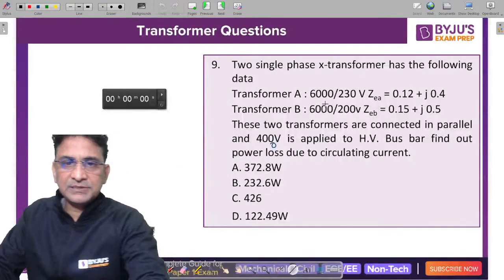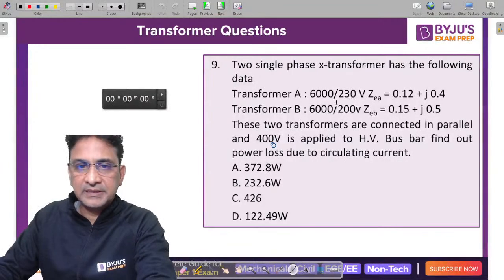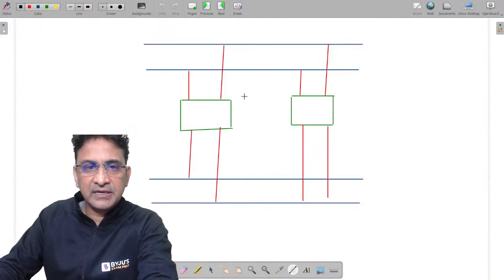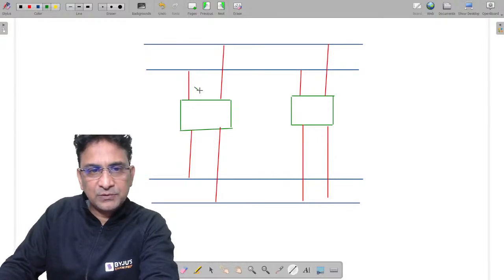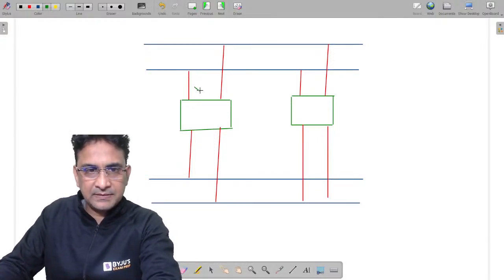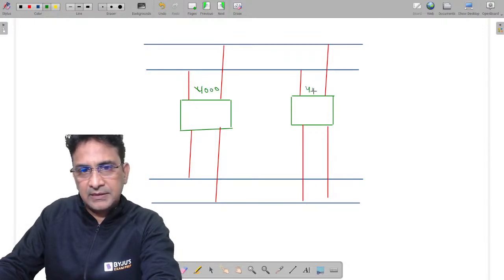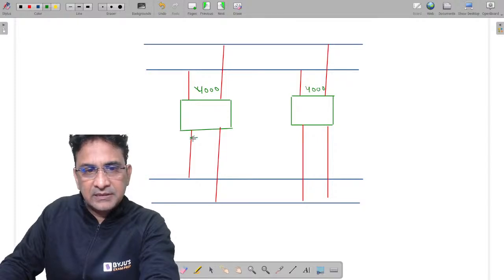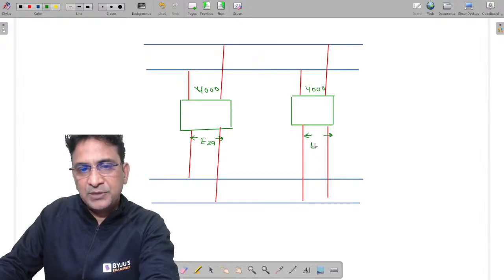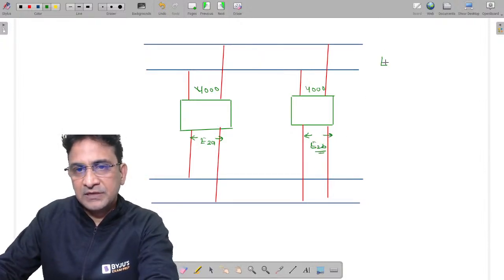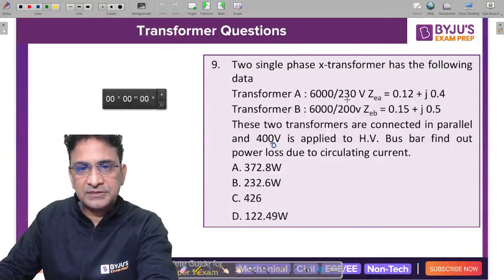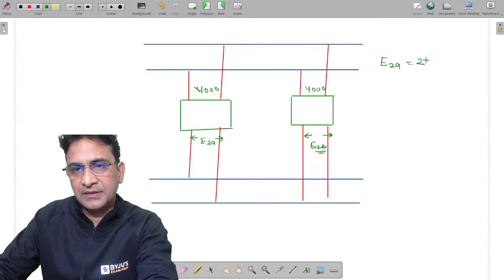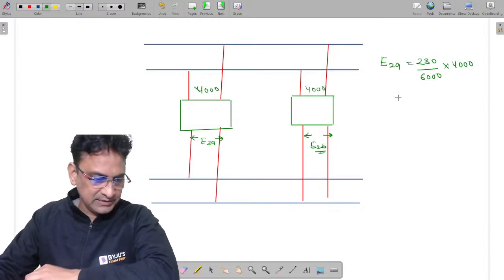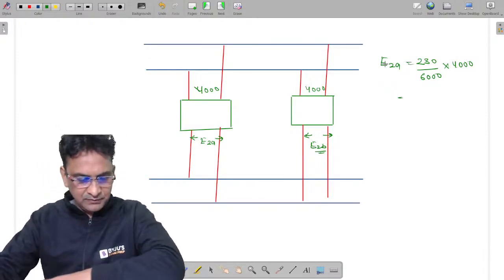Although their turn ratio or voltage rating is equal to 6000/230, we are applying only 4000 volt in the high voltage side. Here we are applying only 4000 volt in the primary winding of both the transformers. Then the induced EMF in the secondary of the transformers is E2A and E2B. So what is the value of E2A? As per the turn ratio, the EMF will be induced. So turn ratio is 230/6000, and we are applying the 4000 input voltage. So this E2A will come 153.33.